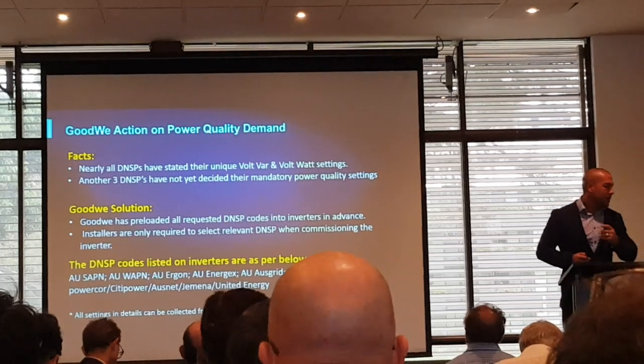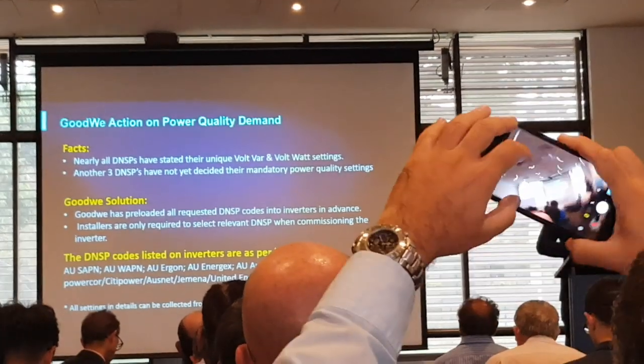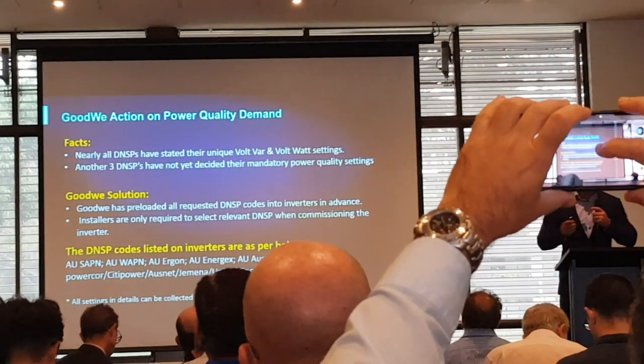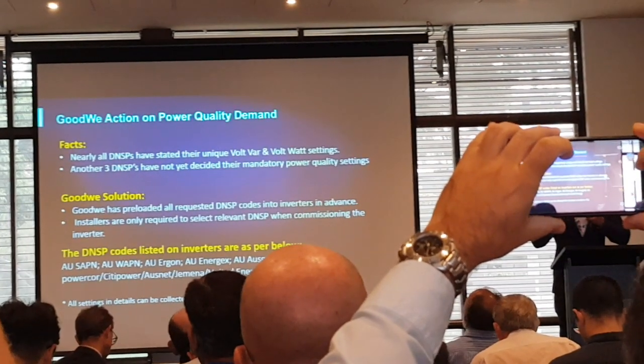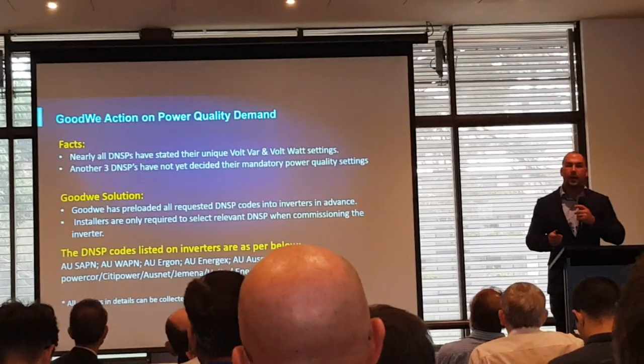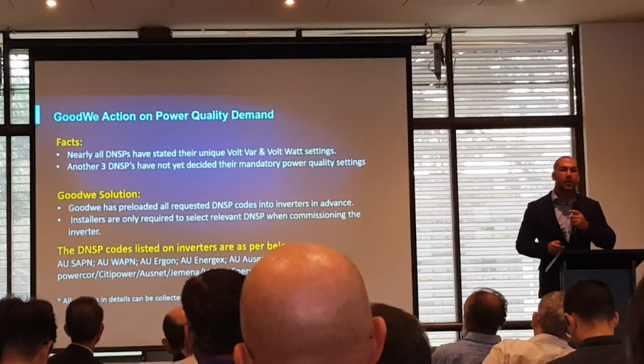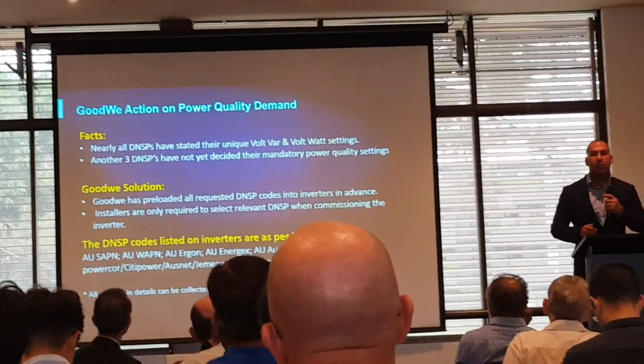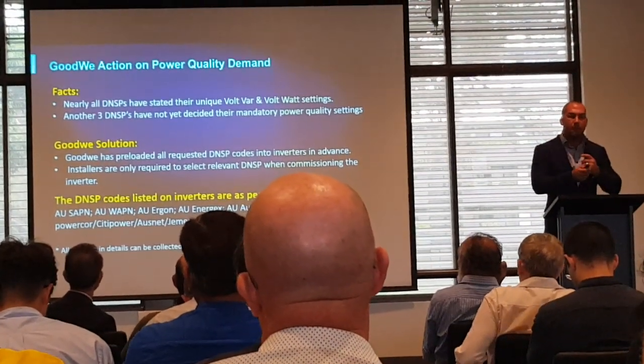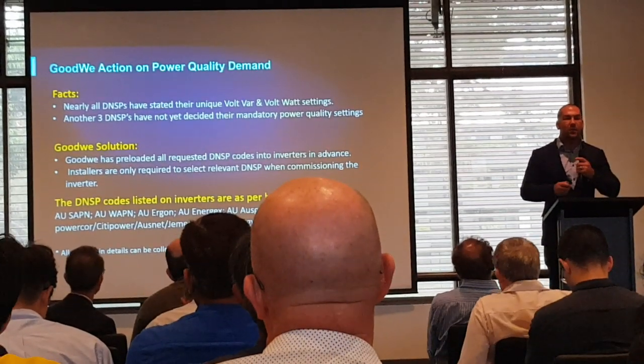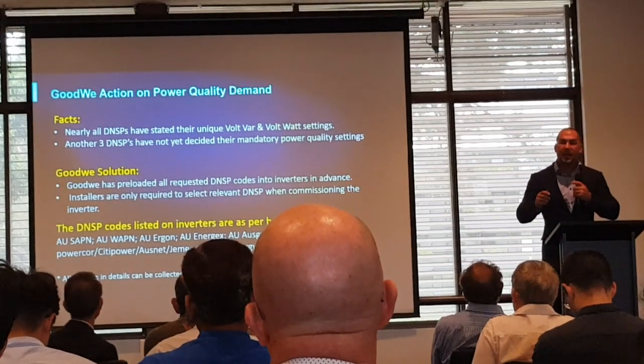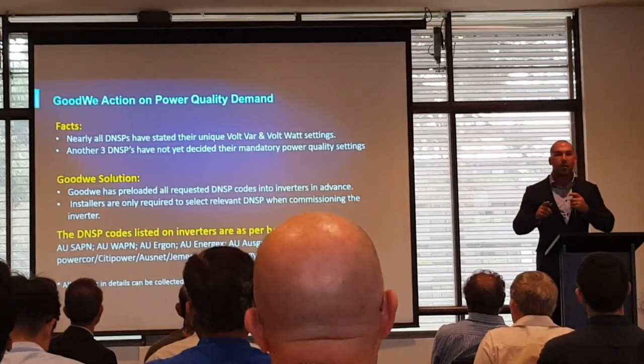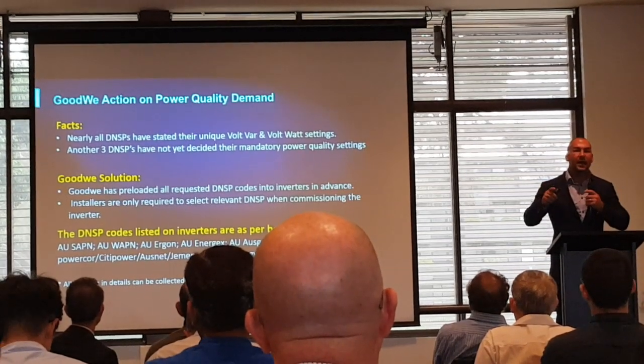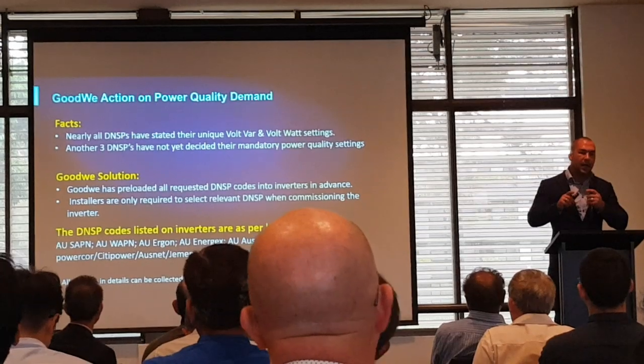On volt var and volt watt, we think we've got the best solution at the moment. All inverter manufacturers need this feature inside their inverter, and we have to give installers the ability to adjust these parameters on site. Instead of the installer plugging in a laptop and Ethernet cable, or using the app to manually program settings, we've loaded all of these settings into the inverter as country codes. So when selecting the country code—say you're in WA—you go down, click AUWAPN, and all your volt var, volt watt settings for AUWAPN are already set.